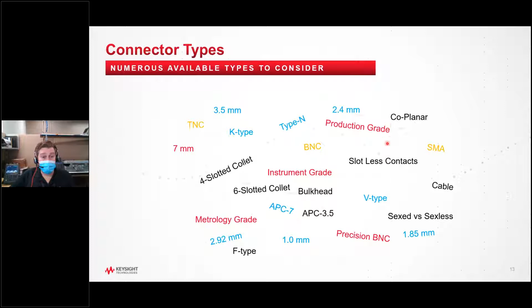The ones that ship with the equipment look a little different than the ones you find lying around on benches. The best case, highest precision option is metrology grade—the most expensive, calibration grade, with the tightest tolerances and most repeatable measurements. On the other end is the cheapest production or general purpose grade, meant for a low number of connection cycles. They're not built to be screwed and unscrewed repeatedly and still provide a repeatable measurement—every use degrades them.